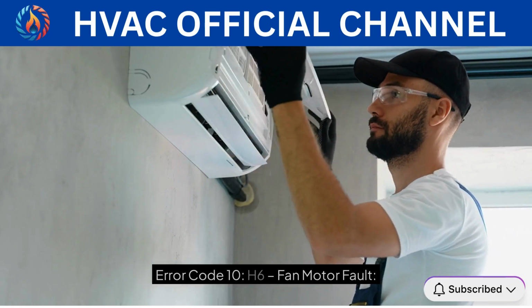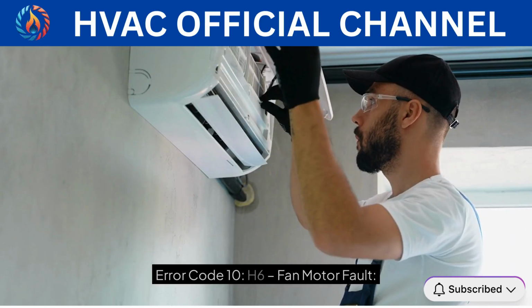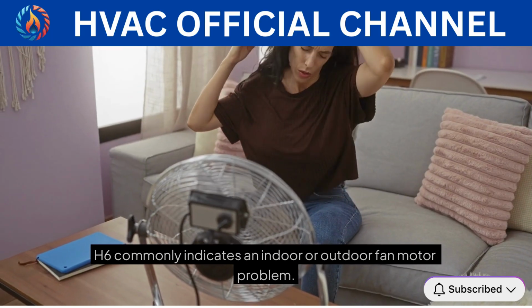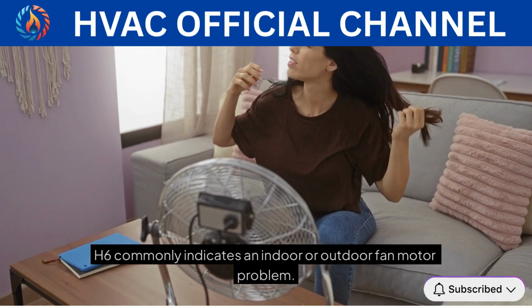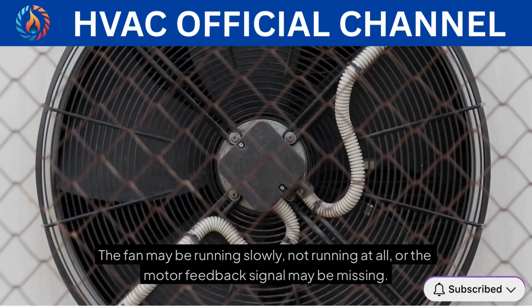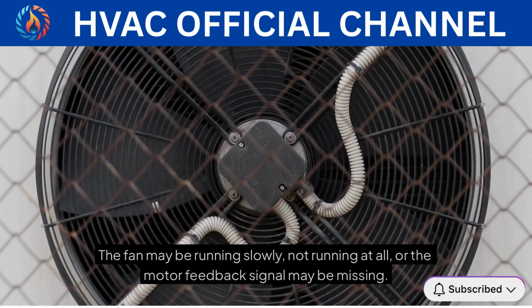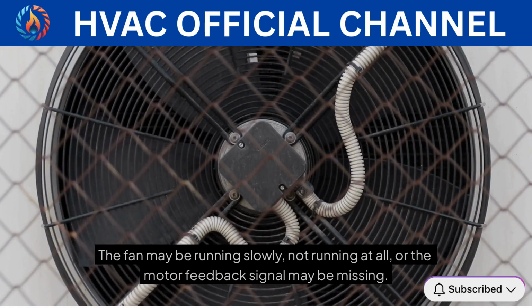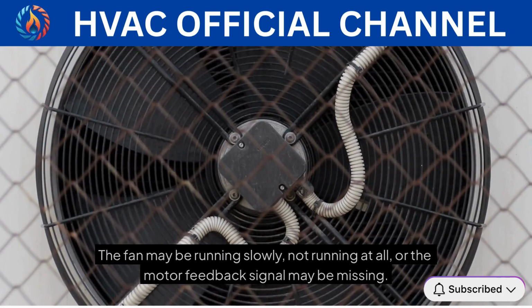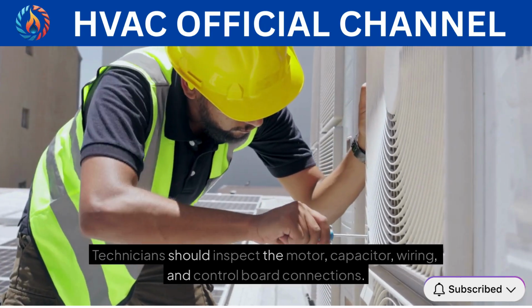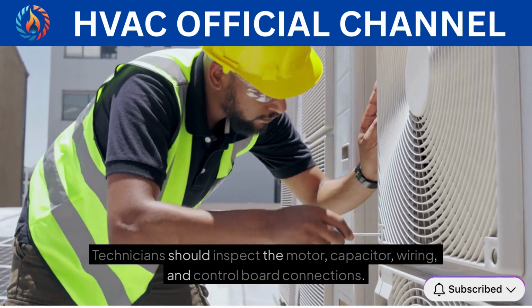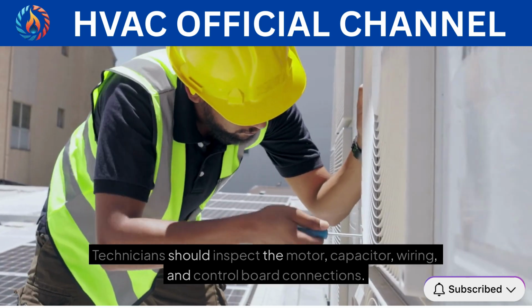Error code 10, H6, fan motor fault. H6 commonly indicates an indoor or outdoor fan motor problem. The fan may be running slowly, not running at all, or the motor feedback signal may be missing. Technicians should inspect the motor, capacitor, wiring, and control board connections.